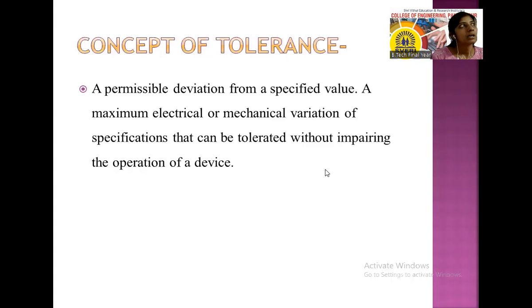This is why a no-load test or reduced voltage test is conducted. Suppose a machine is rated for 230 voltage, but sometimes the voltage may get reduced because of harmonics or other difficulties. So we have to check if that machine is still working at normal speed even with reduced voltage. There may be some cogging effect or crawling effect that we have to check - whether the machine performs well, creates noise, or not. All these things have to be checked.